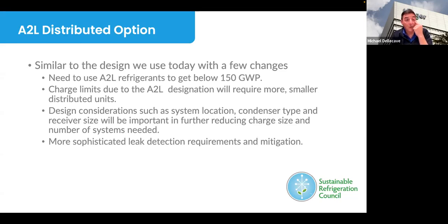So if we start looking at the A2L options, obviously you need to use an A2L, probably most likely below 150 GWP. The charge limits, due to the A2L being a mildly flammable refrigerant by definition, make us look at more smaller distributed units.